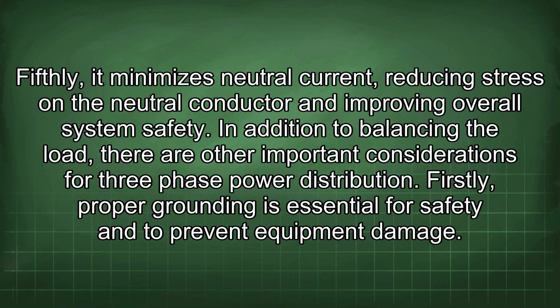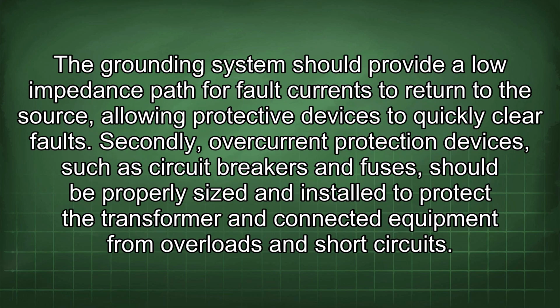In addition to balancing the load, there are other important considerations for three-phase power distribution. Firstly, proper grounding is essential for safety and to prevent equipment damage. The grounding system should provide a lower impedance path for fault currents to return to the source, allowing protective devices to quickly clear faults. Secondly, overcurrent protection devices, such as circuit breakers and fuses, should be properly sized and installed to protect the transformer and connected equipment from overloads and short circuits.